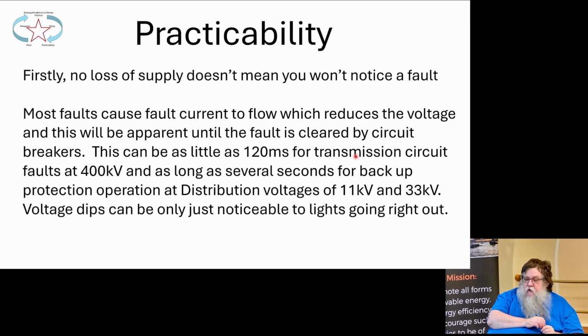Again, it depends on the fault. It's 120 milliseconds for transmission circuit faults, 400 kV. So it's a very, very quick interruption, or dip in the lights rather. But it can be several seconds for some faults on the distribution network.